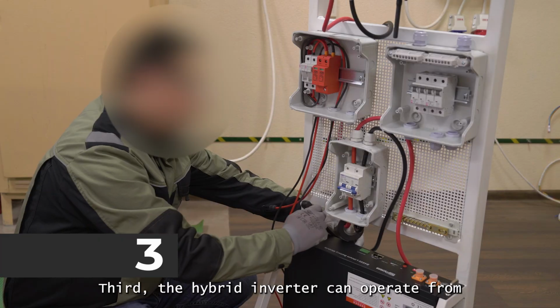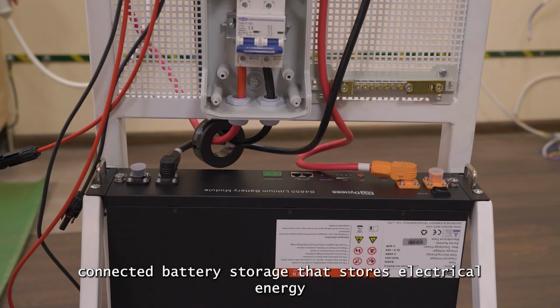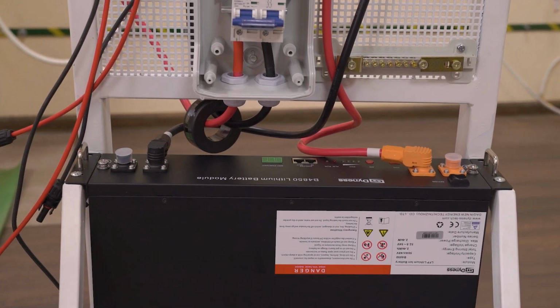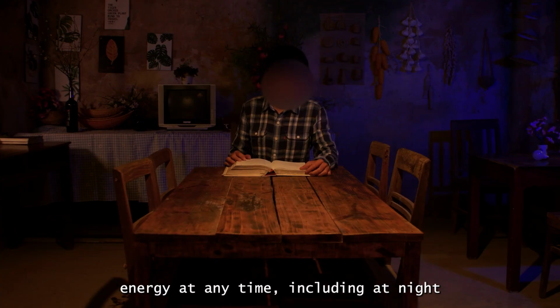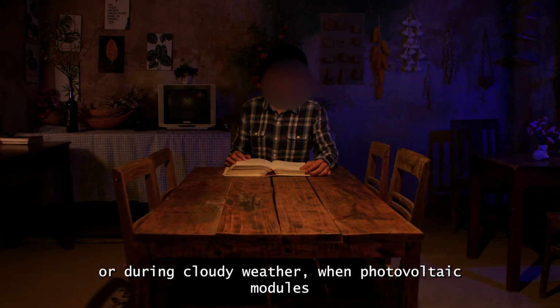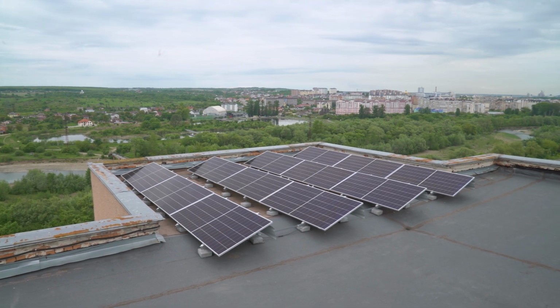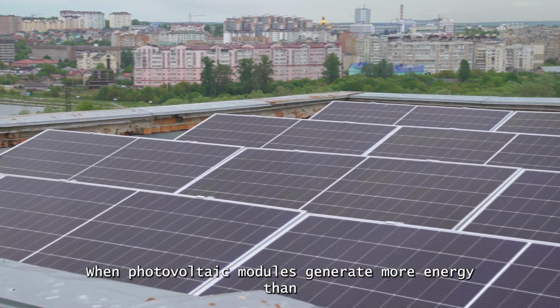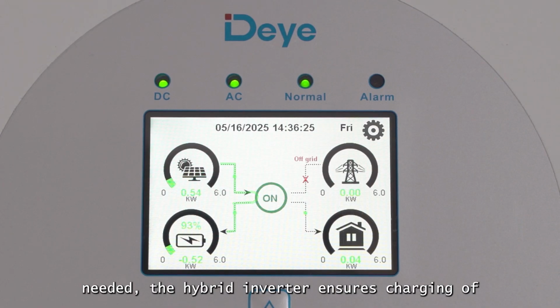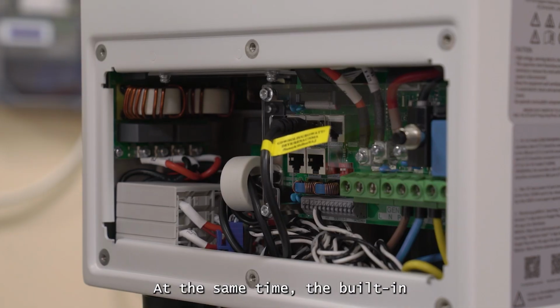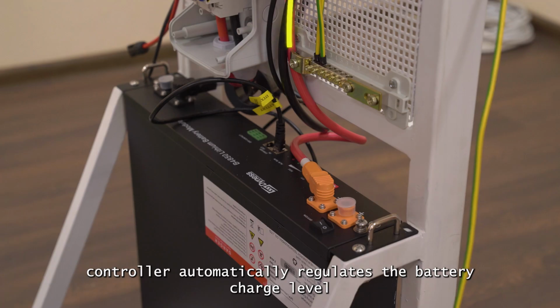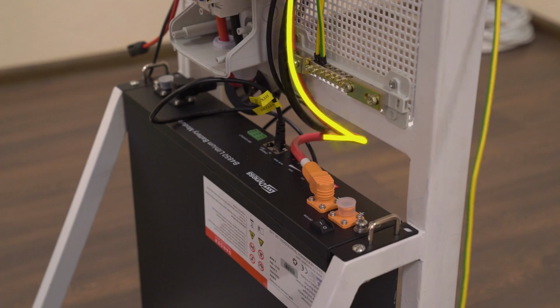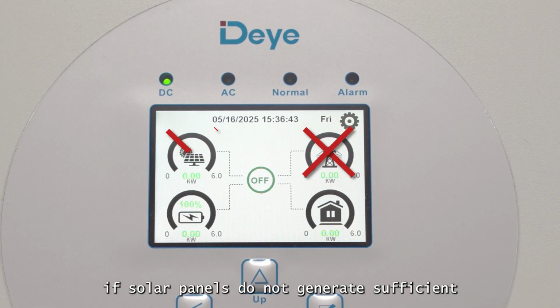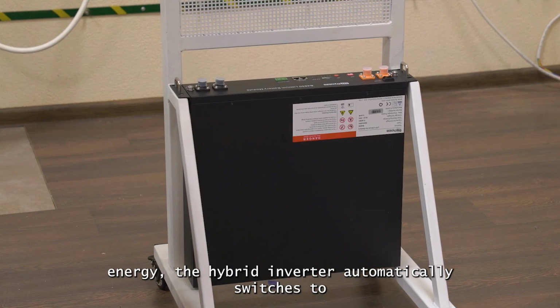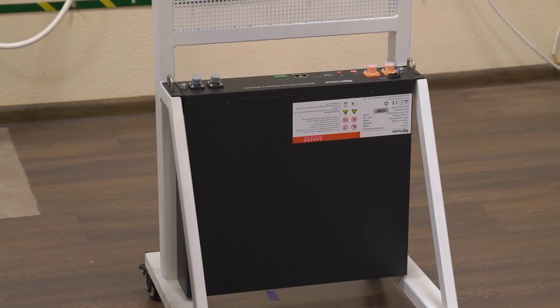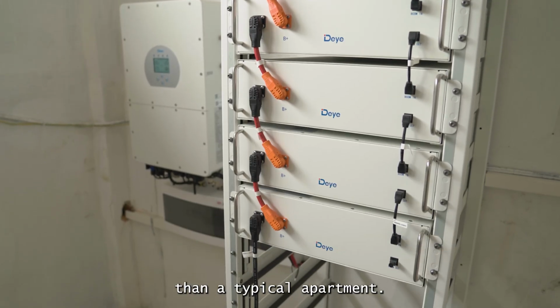Third, the hybrid inverter can operate from connected battery storage that stores electrical energy generated by photovoltaic modules. This allows the use of generated electrical energy at any time, including at night or during cloudy weather when photovoltaic modules are not active. When photovoltaic modules generate more energy than needed, the hybrid inverter ensures charging of connected battery storage. At the same time, the built-in controller automatically regulates the battery charge level to ensure their efficient operation. In the absence of grid power, and if solar panels do not generate sufficient energy, the hybrid inverter automatically switches to battery storage. This system is designed for larger facilities than a typical apartment.